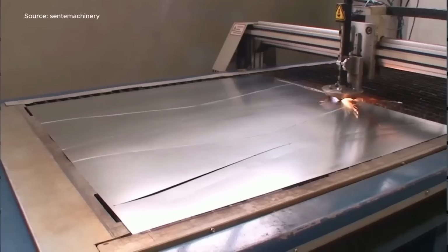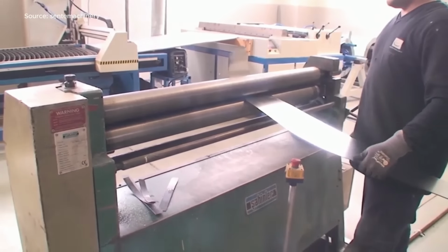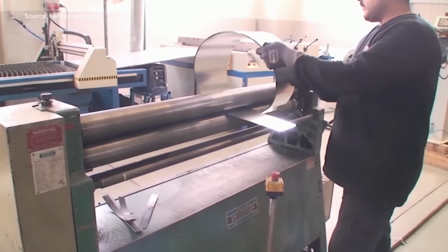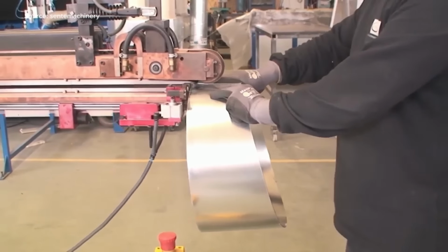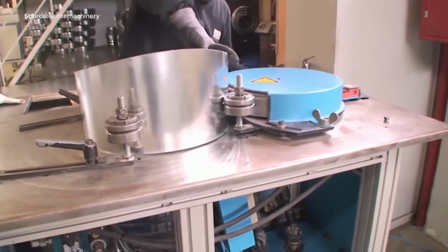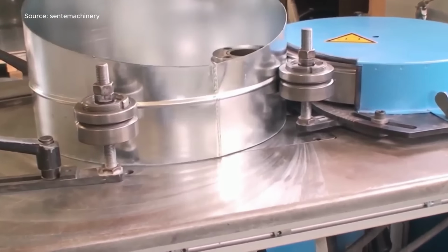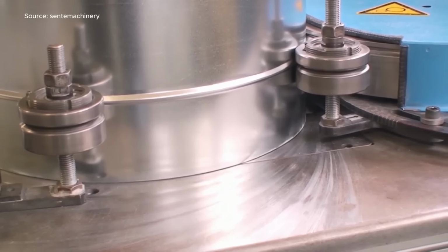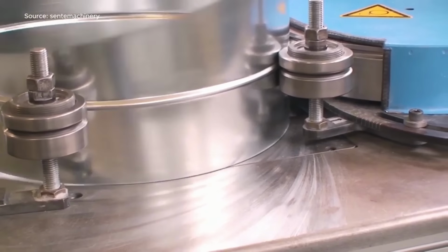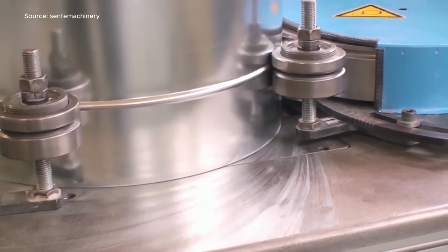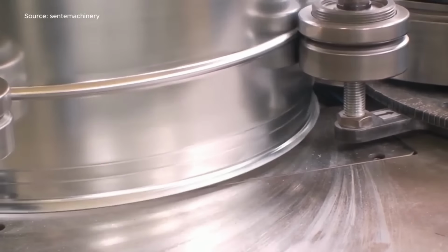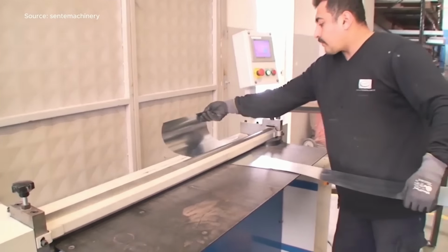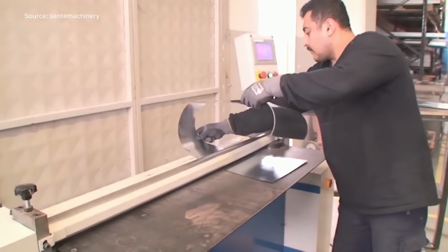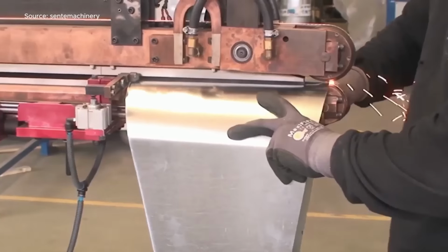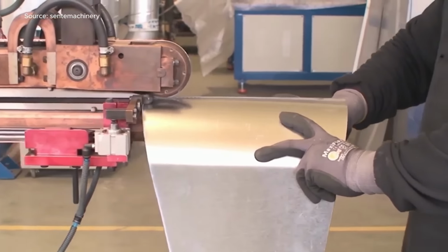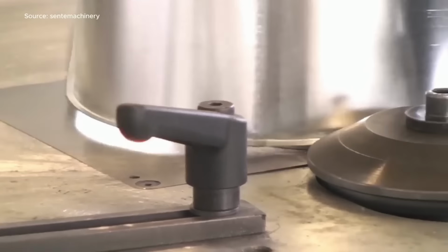Oval ducting, sleek, efficient, and often hidden behind walls or ceilings. But shaping flat steel into this aerodynamic form takes more than just force. It takes engineering. It begins with feeding coiled sheet metal into a line of forming rollers. Step by step, the flat strip bends into a circular tube. A spiral lock seam is created during the roll-forming stage to hold the shape tight. Next, a hydraulic press flattens the round tube into an oval profile.